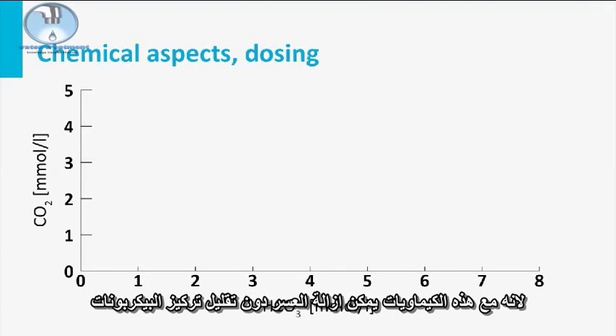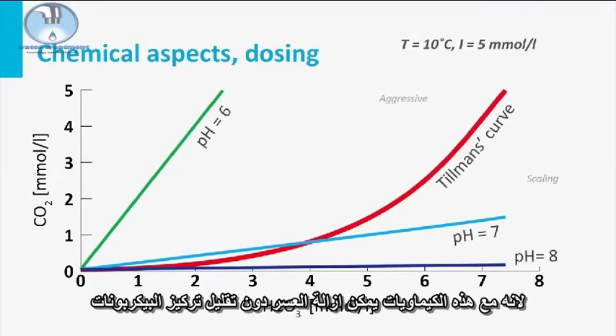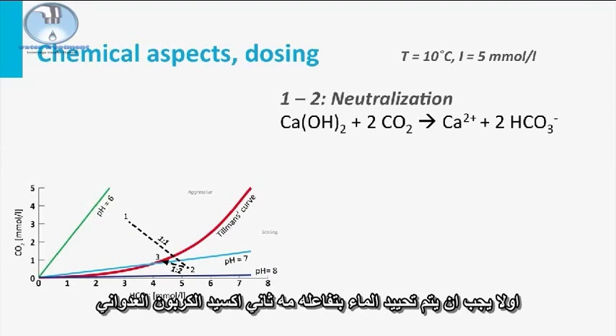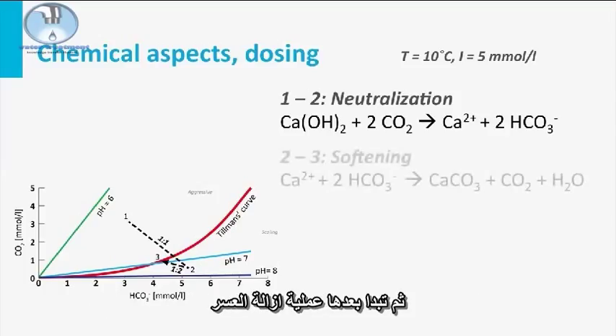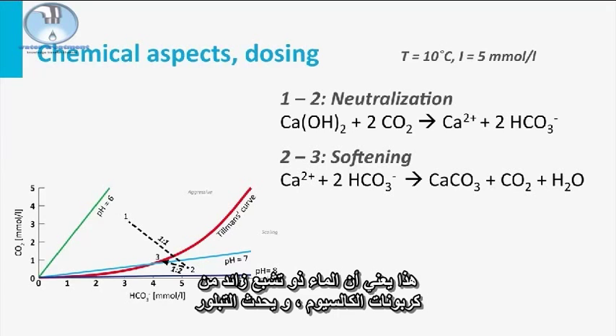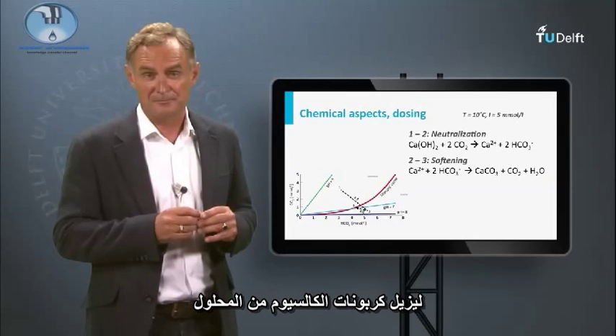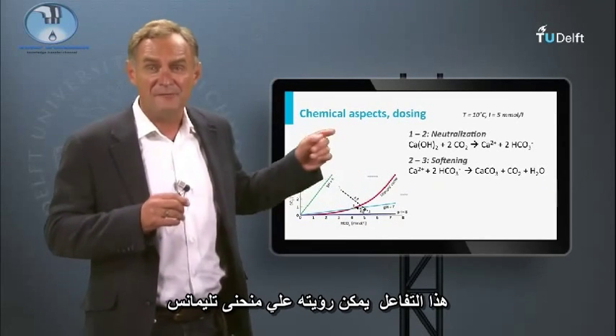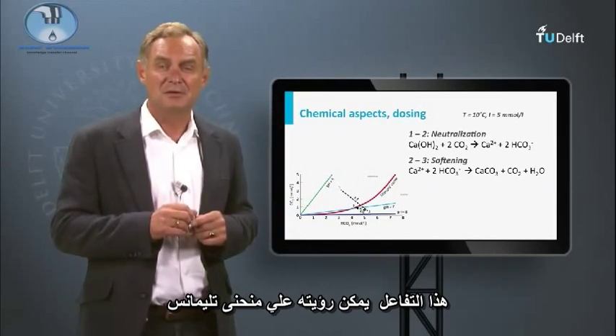When lime or caustic soda is used for softening, two different reactions can take place. First, the water should be conditioned by reacting with the aggressive carbon dioxide, and then the softening process will take place. This means that the water is supersaturated with calcium carbonate and crystallization occurs, removing the calcium carbonate from the solution. These reactions can be visualized in the Tillman's Curve.